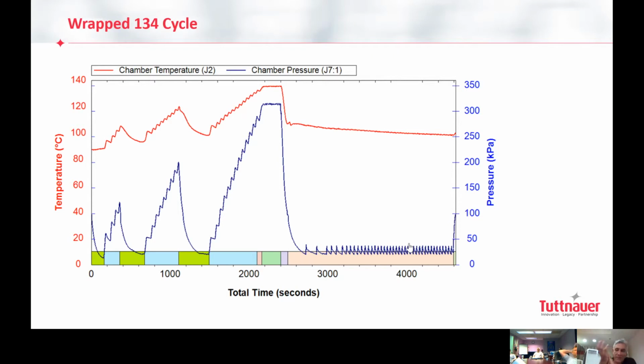if we are using synthetic material, when we pack in synthetic, it becomes very important. You have to understand, we used to use the class S. In the class S, if it's not dry, you leave it a little bit with the open door and all good. It's not working anymore, gentlemen. If we're following the standard and keeping the class B standard by the EN 13060, then it has to come out by the rules, 99% dry. That's why we have to find solutions for many types of packing material.